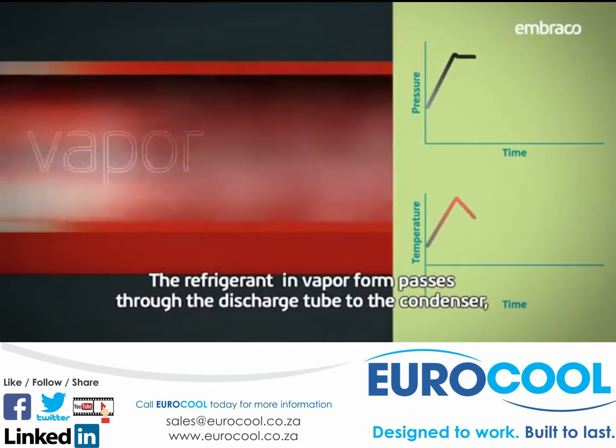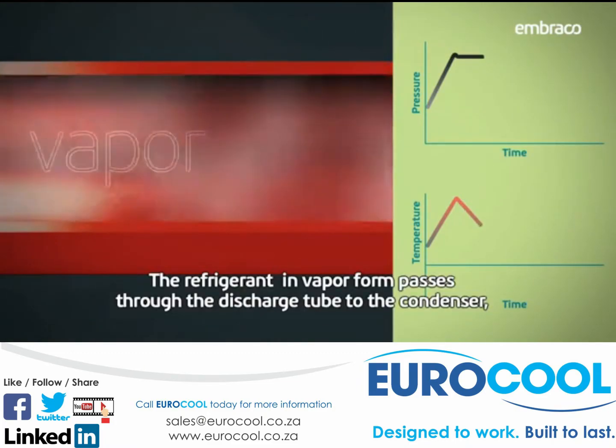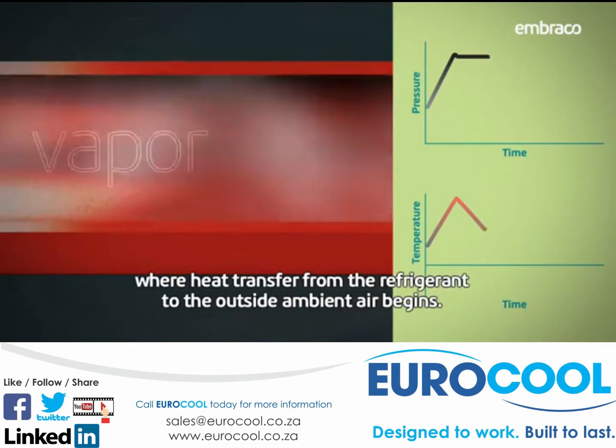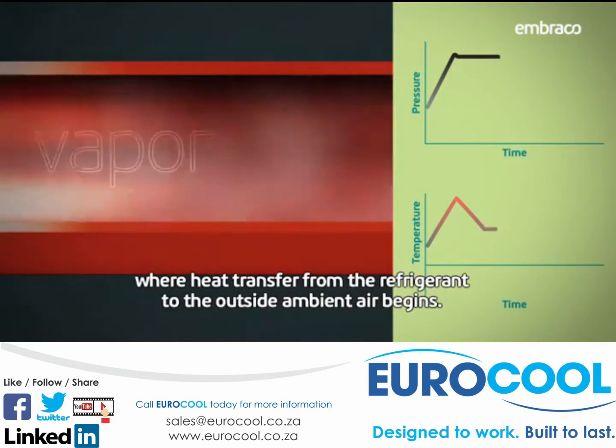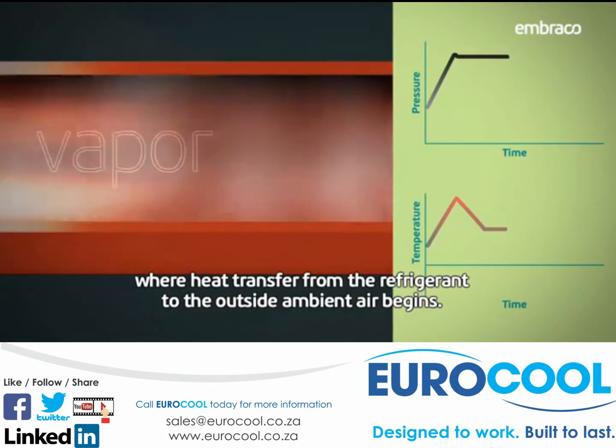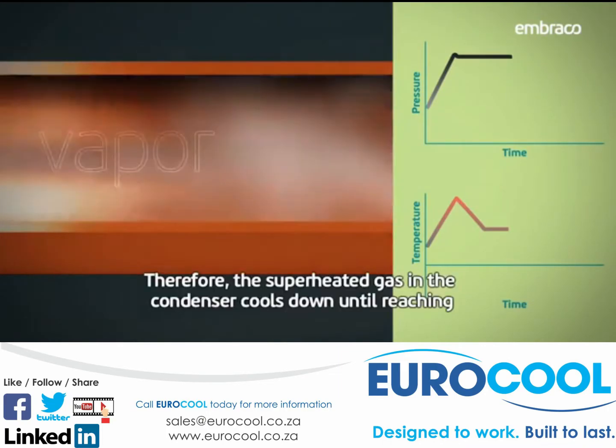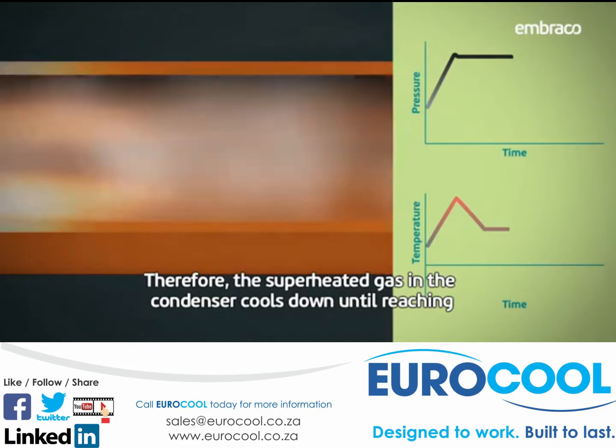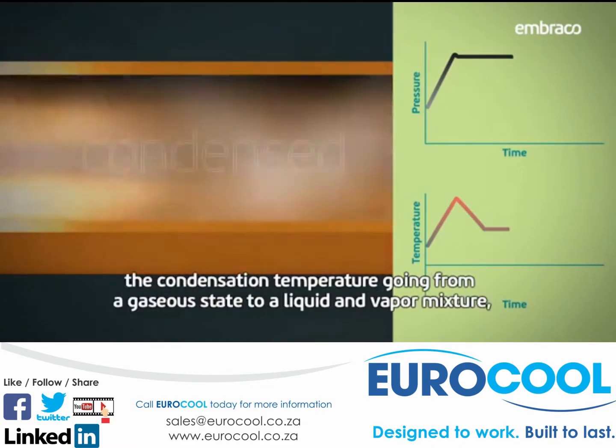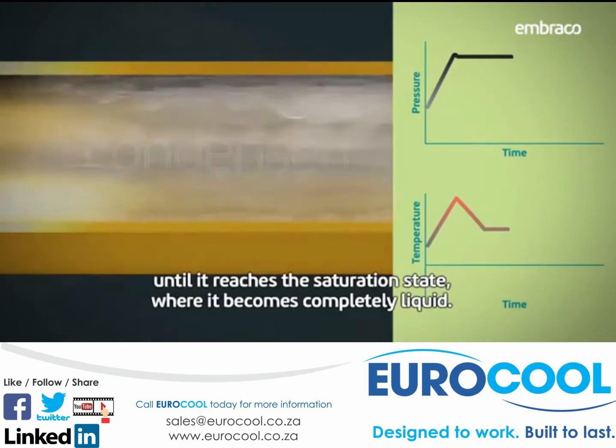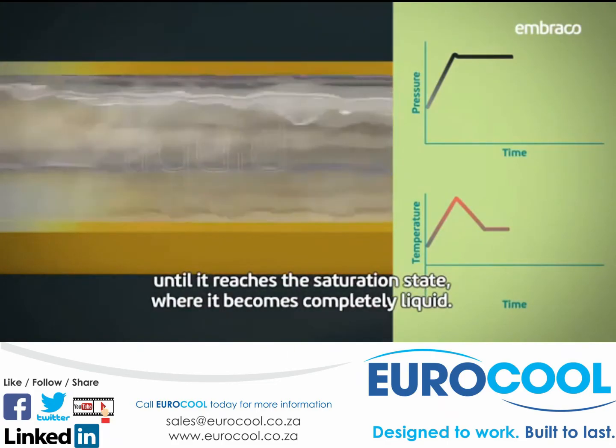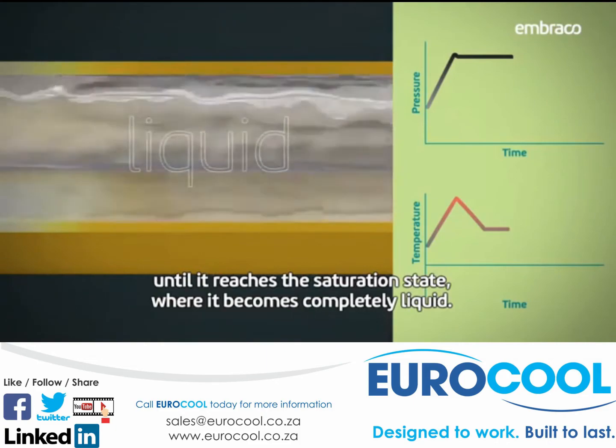The refrigerant in vapor form passes through the discharge tube to the condenser, where heat transfer from the refrigerant to the outside ambient air begins. Therefore, the superheated gas in the condenser cools down until reaching the condensation temperature, going from a gaseous state to a liquid and vapor mix, until it reaches the saturation state, where it becomes completely liquid.